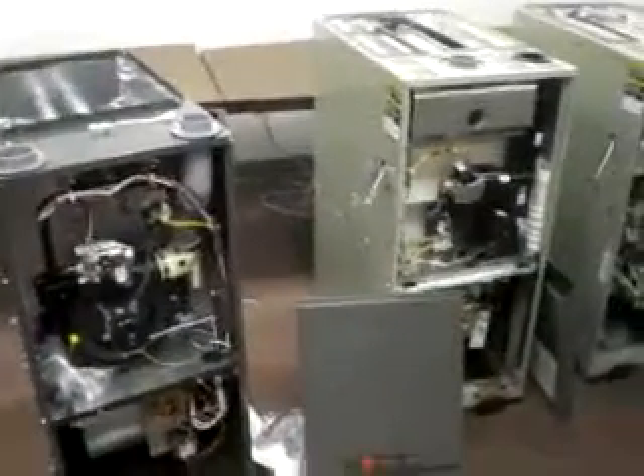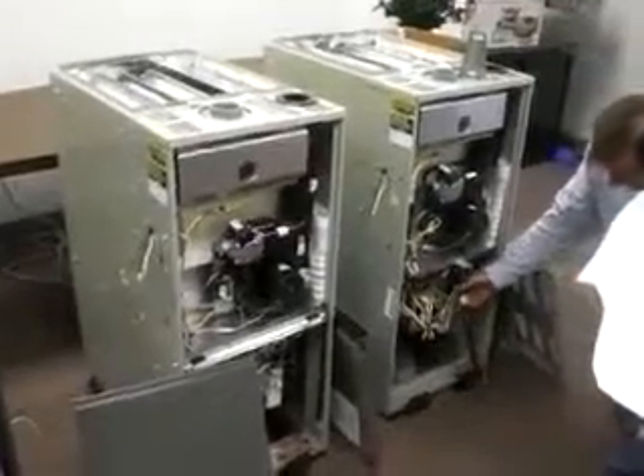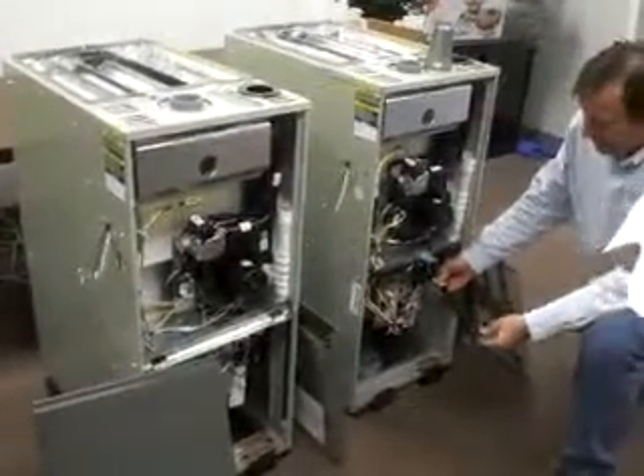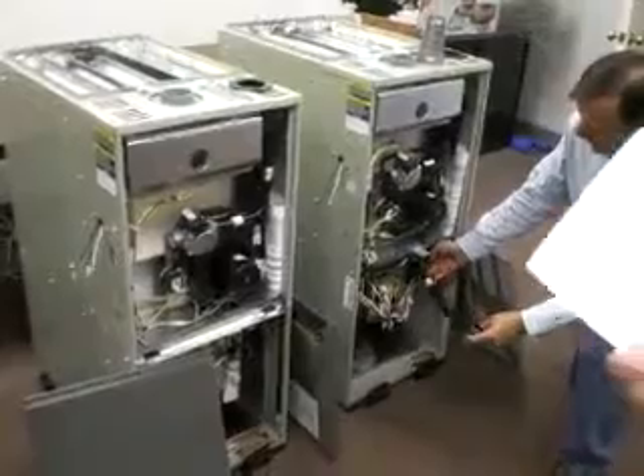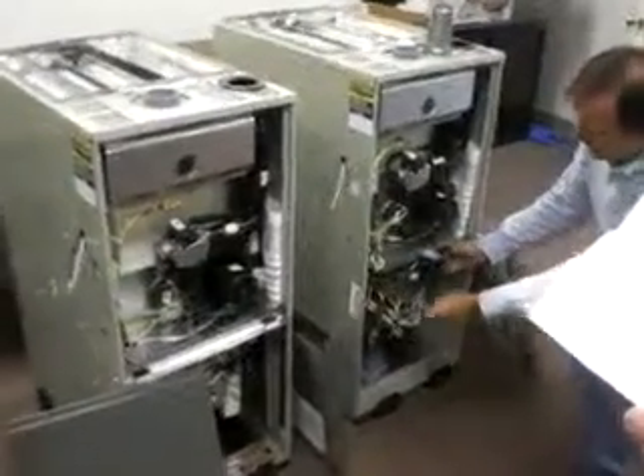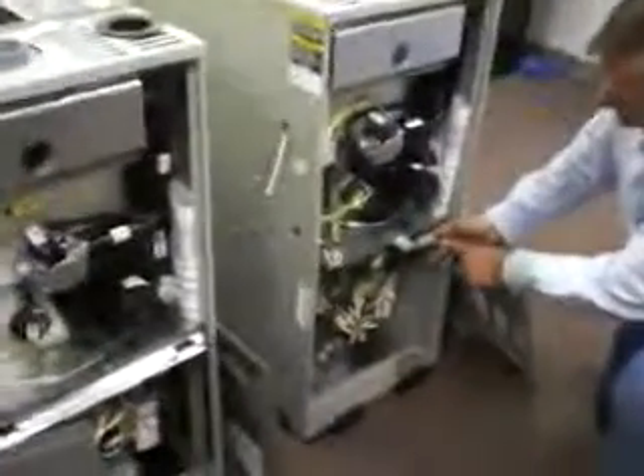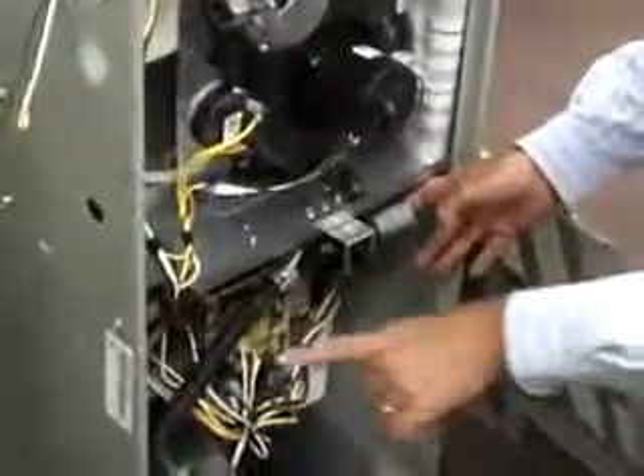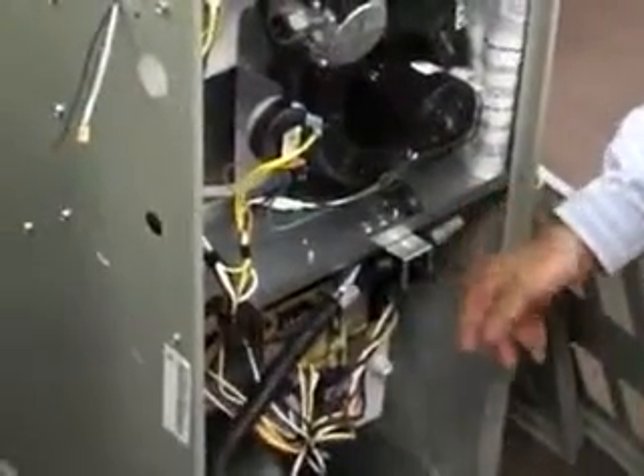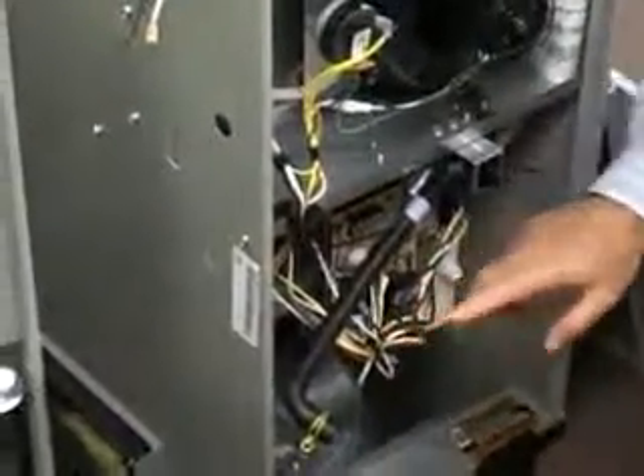All of our furnaces come with the trap assembly assembled and a ready-made and ready-to-install connector pipe. Comes complete with the clamp and a PVC adapter to adapt to a common PVC drain. All we have to do is use the knockout at either side of the furnace if we're going to go on the right side or the left side.